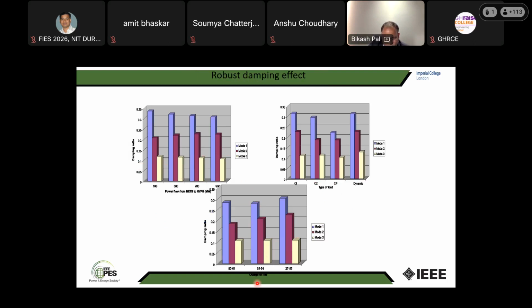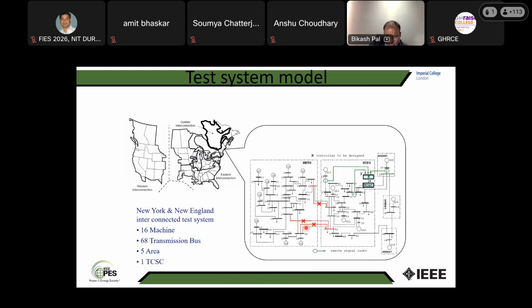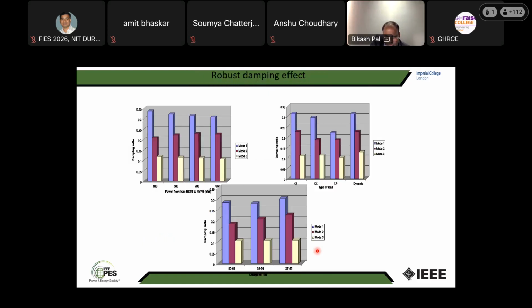Now let's test this for line outage. When the line is out between 60, 61, 53, 54, 27, 53. So these are all the lines, then bus numbers between the areas. Like 60 in one area, 61 in another area. 61 is here, and 60 is here. Then 27 is area 1, and then 53 is area 2. And then 54, 53, like this. So between these 2 buses, if some of the circuits are out, what happens to the damping? Now the dampings are again more than 10%. 10% damping for a 0.3 hertz, 0.35 hertz mode means within 5 seconds, your oscillation will settle down.